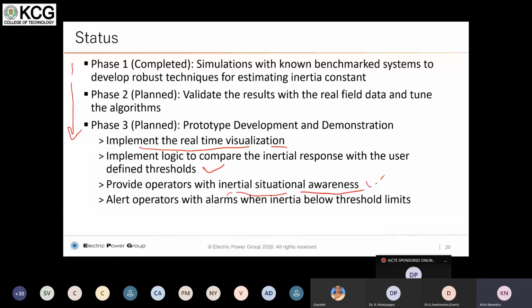What do I mean by that? If you take your equation P equals V1 V2 divided by X times sine delta, where delta is the difference in phase angle between the two ends of the line. In power systems, V1, V2 and X are pretty much constant or controlled. V1 and V2 are controlled, the voltages are controlled, and X is constant in your system. Therefore, the power flow is directly proportional to sine of delta. That means if the phase angle is more, the power is more, and the phase angle will be higher in electrical process.